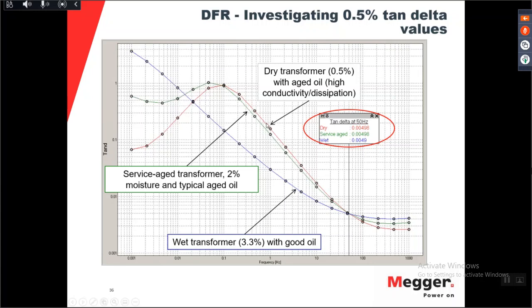Well, this red one, it is a very dry transformer. The moisture content in the paper is very low, but it has a very poor oil. The oil has absorbed some bad particles, giving rise to a high conductivity in the oil. So the oil gives a very, very high response here, but the paper in the lower frequency range and in the higher frequency range gives a very low response.